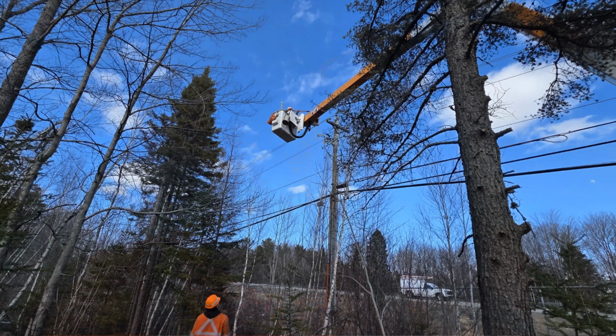There was no pad mount transformer outside. The school has their own switch gear internally. So I did a few quick checks. We checked the electrician was on site. There was no damage inside on the terminations, same thing with the outside. It was in the woods, there was a lot of debris on the ground. Couldn't see if there was a squirrel or something that got into the live lines.